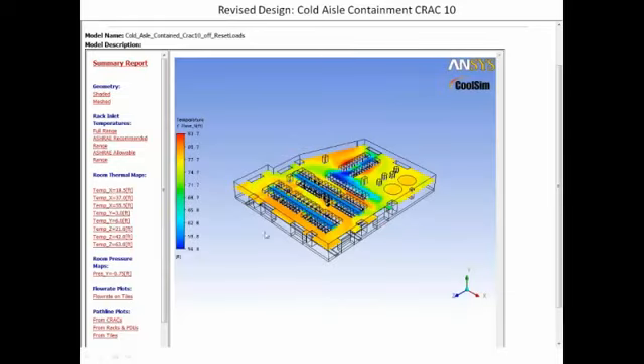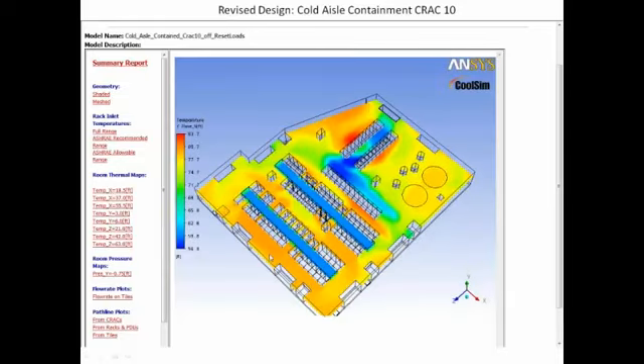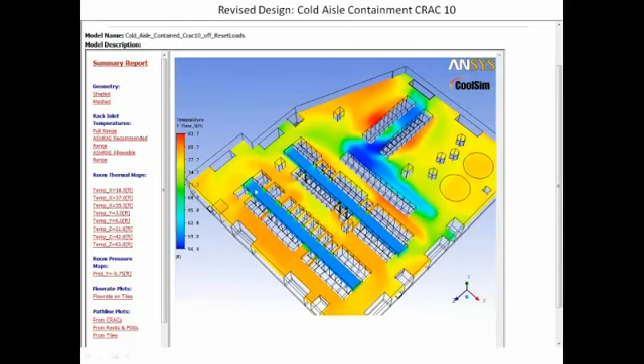Yes. And furthermore, in cold aisle designs, there's a human factor issue. I'm showing it here. This is a slice right through the data center at 6 feet. And because the cold aisle is fully contained, it's of course cold, but there's rarely anybody in there. Humans are walking around in the hot aisle because the room has become the hot aisle. And you see here the effect, the temperature, now we're pushing it up into the high 80s, low 80s, high 70s, low 80s. And the cooling units love that because the big delta T across the cooling unit means an efficient cooling unit and a low energy consumption on the cooling unit. However, the human is going to get nervous.